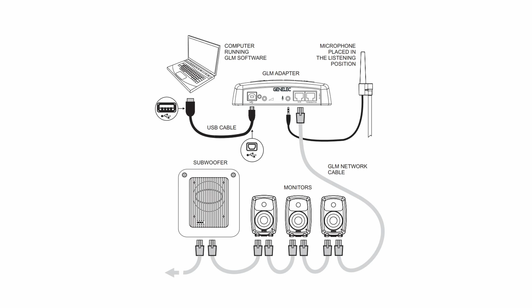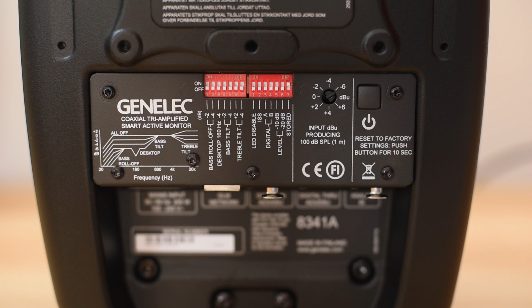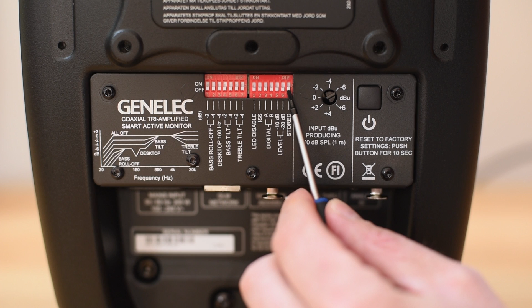Always check the position of the stored dip switch, because it has to be set to on to use the saved settings in standalone mode without GLM. Otherwise, the saved settings will not be used. There are a few models that don't have dip switches, for example the 8320 and 8330 - these will always use the saved settings. But for all the bigger models, make sure that this dip switch is set to on.